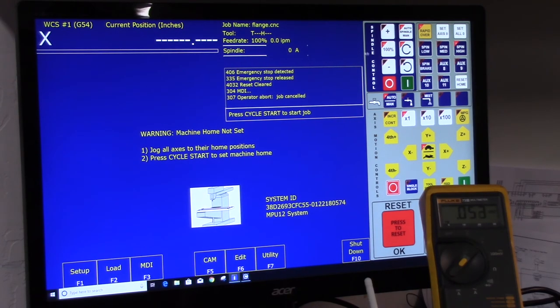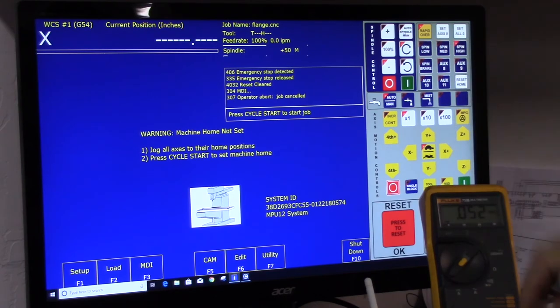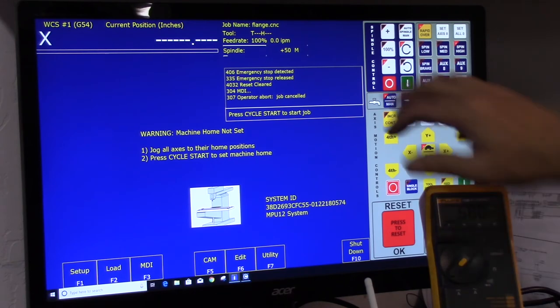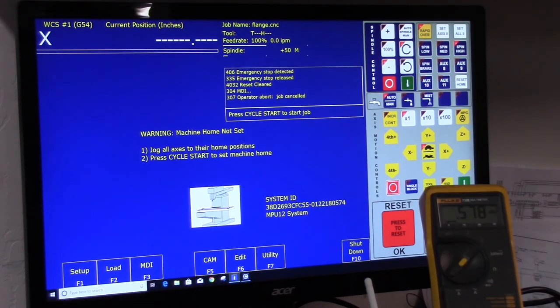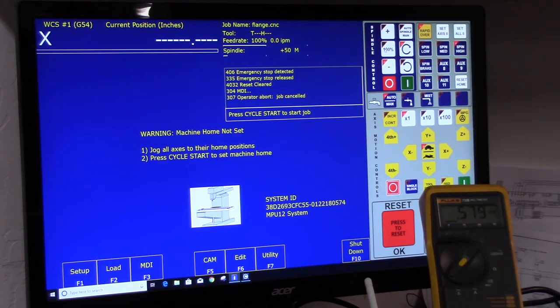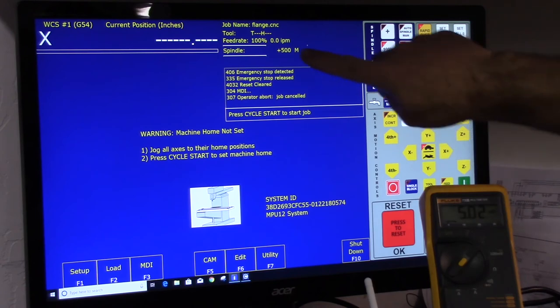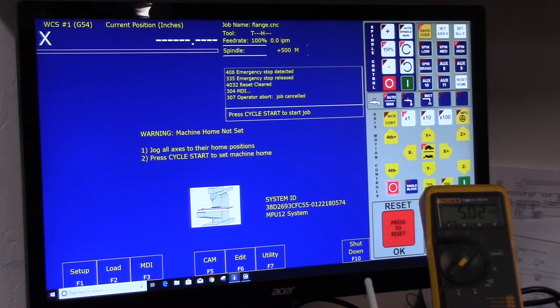You can also go up here to the spindle control panel, virtual control panel. You can take it out of auto, click on it. Now it's in manual mode. And then you can hit the green button up here. That turns the spindle on. And you'll notice here it says 50 RPM. Let's go to 100%, which is half the spindle range. It says 500 RPM here. And we got 500, or we got 5 volts DC here.